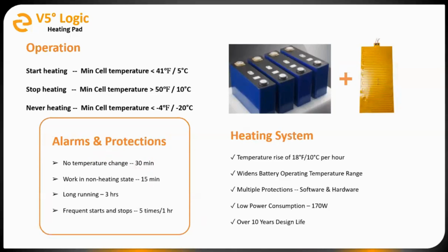Also, if the battery detects that the heating pad is running for 15 minutes or more when we have not hit this minimum cell temperature, that will actually cause the fuse on the heating pad to blow, and it basically takes it out of the circuit completely. So this is maybe one of the more serious alarms or protections. And again, the battery knows the heating pad is on, it's heating, it's increasing the temperature, but we never achieve this minimum cell temperature to begin with. So the battery is going to say, let's protect the cells. We don't want to be heating our insides when we don't actually need it.